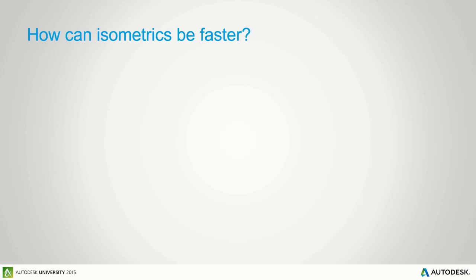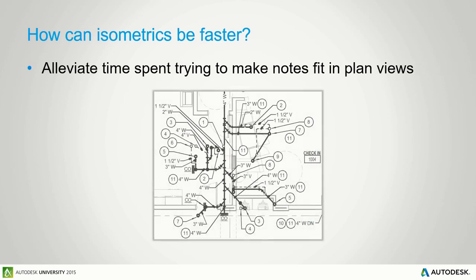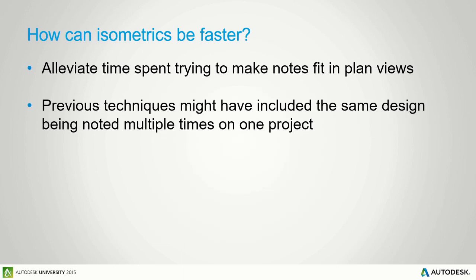We find isometrics are actually a lot faster than trying to cram plan notes to convey all the design intent we need for code review and contractors. We can alleviate a lot of the time spent on repetitive notes. For example, if you have a four-inch sanitary going up and down through multiple floors, you'd have to note that same thing on every floor. If you have it in an isometric view, you see that information and don't have to convey it with a note each time.